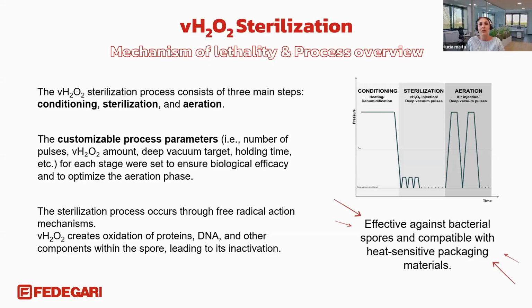And finally, during the aeration stage, the residual H2O2 is removed under controlled conditions in order to reduce the concentration in the chamber and in the load below 1 ppm.